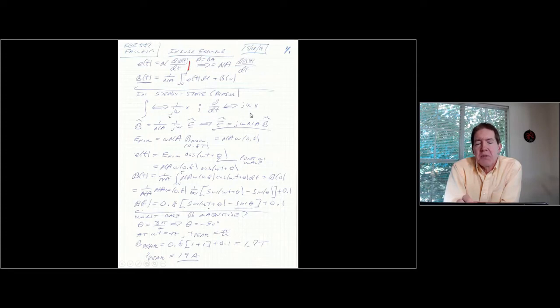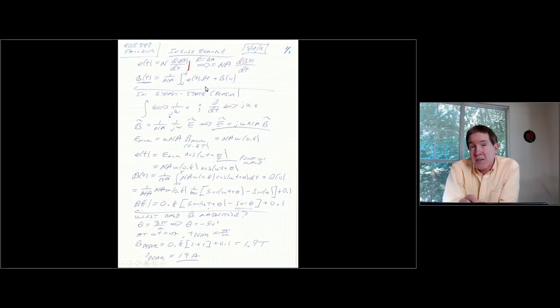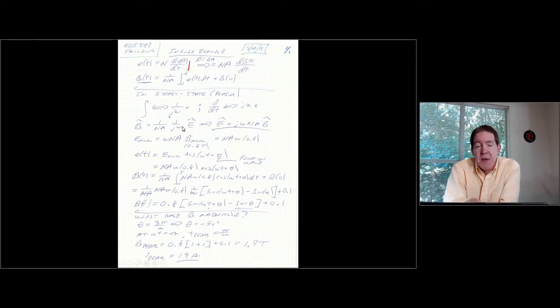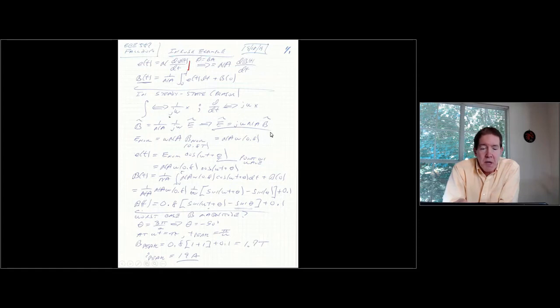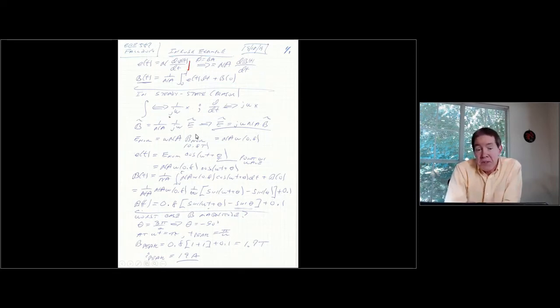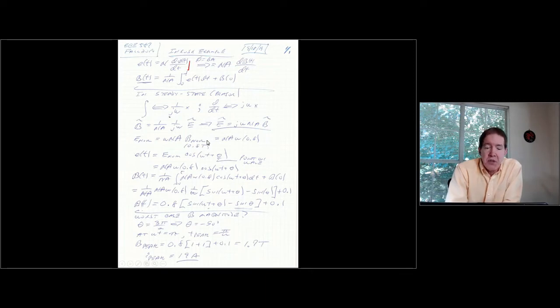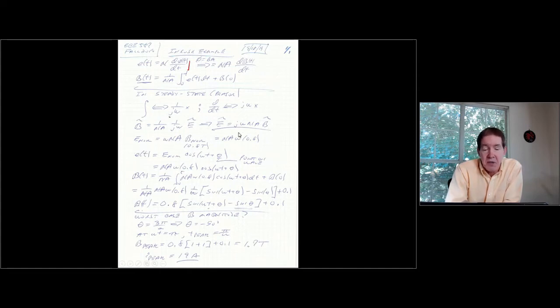A derivative corresponds to multiplying by jω. So for the relationship where B is the integral of voltage, in phasor steady-state analysis, B = (1/NA)·(1/jω)·Ẽ, which gives Ẽ = jω·NA·B. The reason I'm doing this is I want to relate the 0.8 Tesla nominal value to E. So if my nominal operating flux density is 0.8T and I multiply by ω·N·A, this gives me E nominal, which I can use.